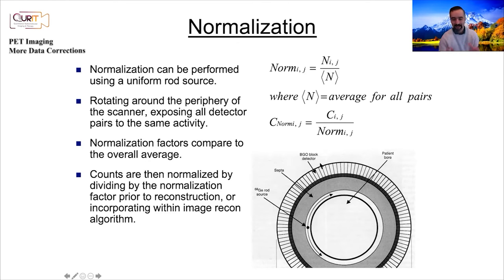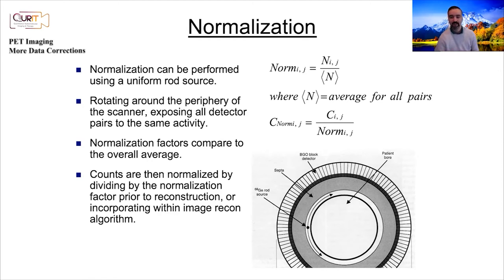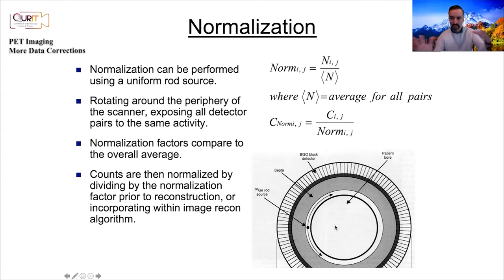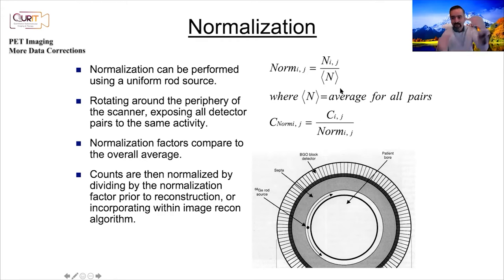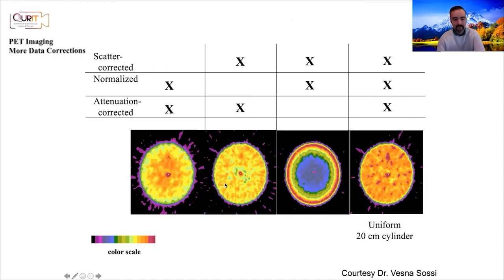Increasingly, people also incorporate normalization into iterative image reconstruction rather than pre-correcting the data. It used to require a very long scan, but more sophisticated so-called component-based normalization approaches use more mathematics and geometric modeling, requiring fewer counts to perform the calculations. The essence remains the same: a rotating rod source covers all lines of response and you estimate the effective sensitivity and normalization factors.